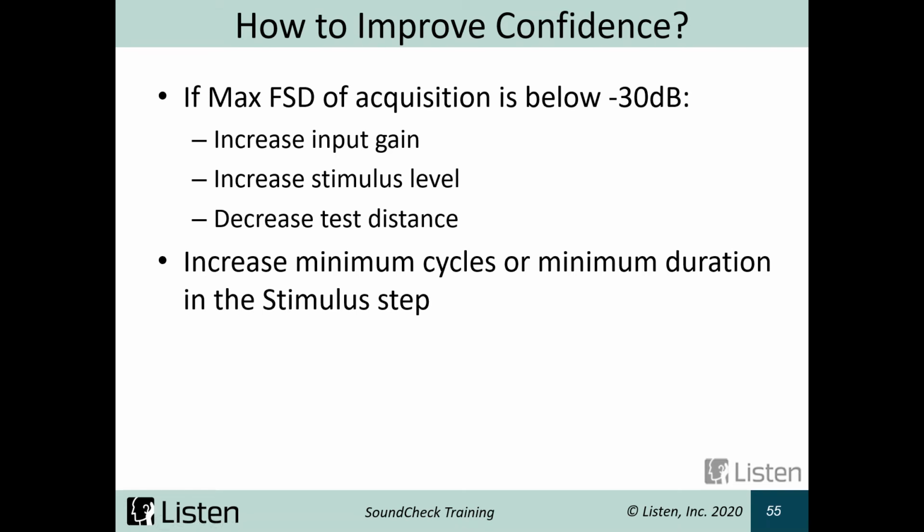This becomes a pretty large give and take, especially during production. If you're doing production tests, you're often in a noisier environment and time matters a lot more. So it becomes a little tricky to decide how long my stimulus should be before I'm having negative impact from that.